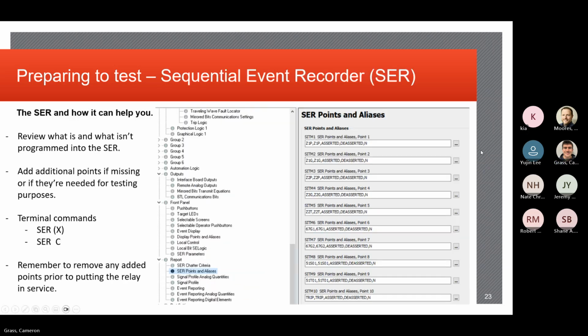Perfect. Going over the SER data again, as I previously mentioned to Brian, this is data that we'll export before we even start testing, and have that as a backup to provide to the client in the event that something happens, say a fault were to occur while we're doing our relay testing and that relay is out of service. We have the event recorded data previous to that to make sure that that relay doesn't communicate with anything else.